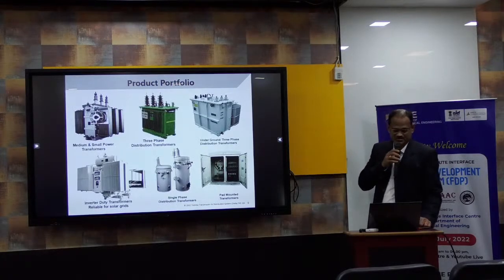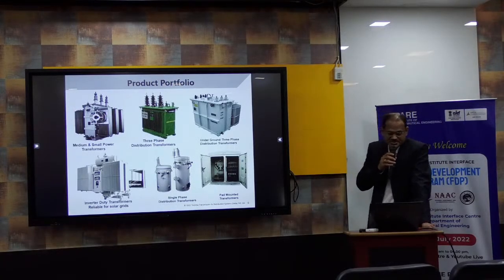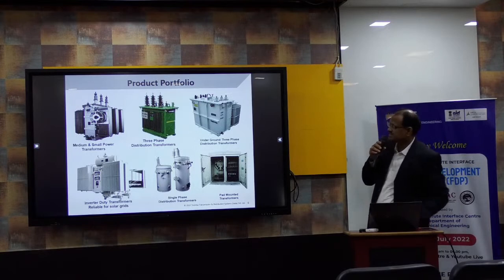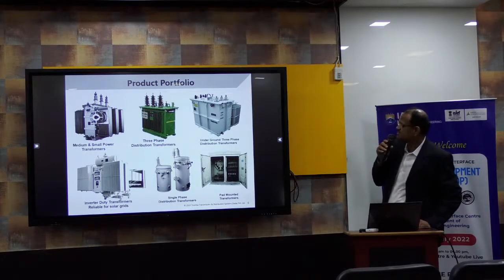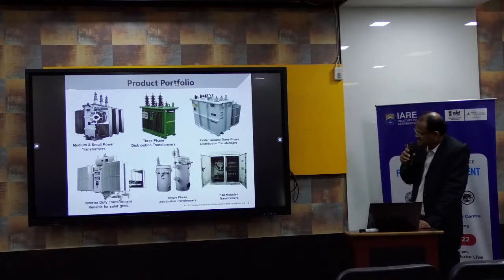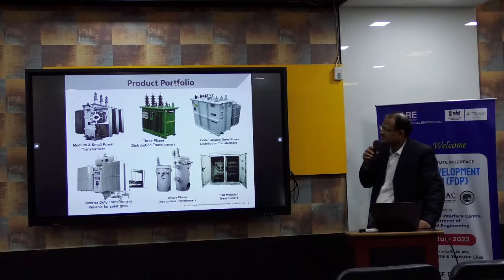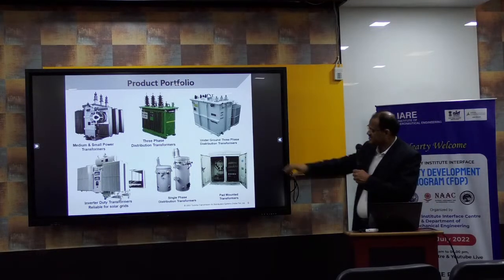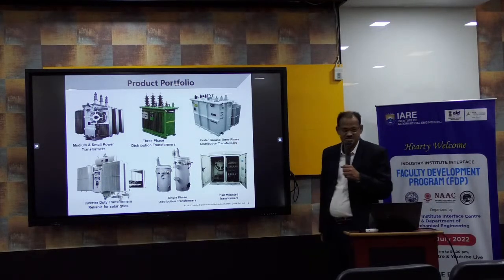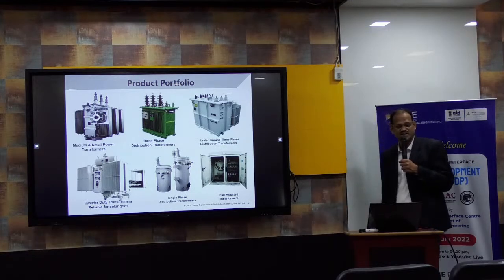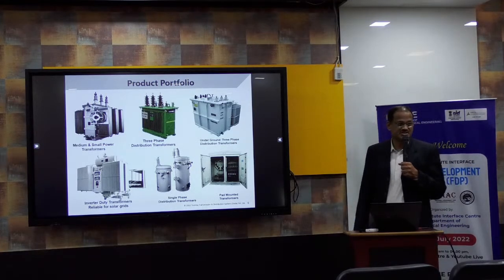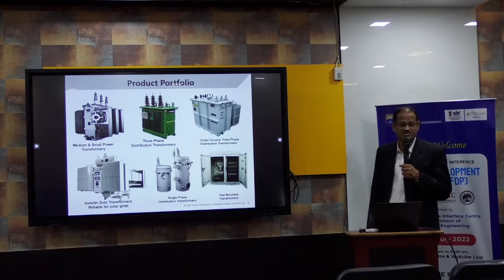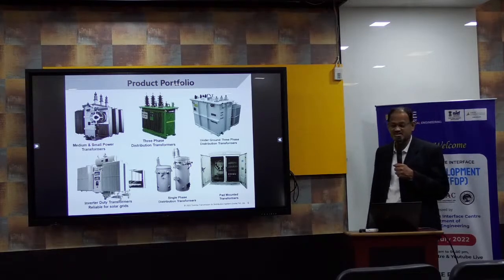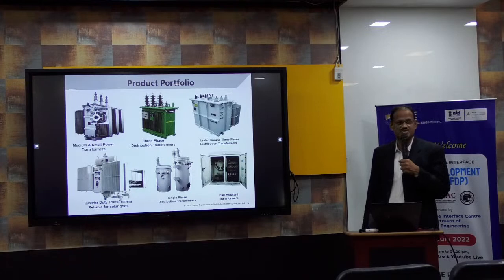This is the product portfolio photos. The first one is medium and small power transformer. The second one is 3-phase transformer, third one is underground 3-phase distribution transformers, and inverter duty transformers, single phase transformer, or pad mount transformer. I try to emphasize on underground transformer. What underground means: in case of totally like water is submerged, the transformer is submerged in the water also, it won't fail. That is the technology required in underground transformer.